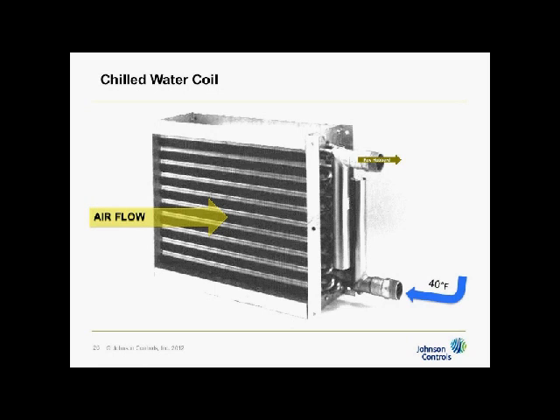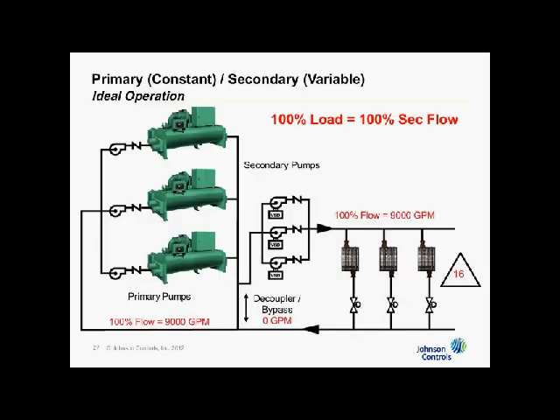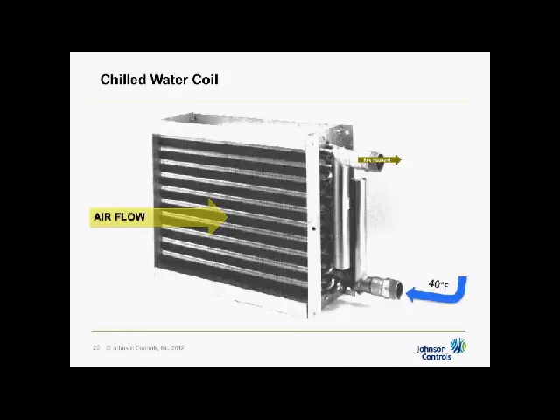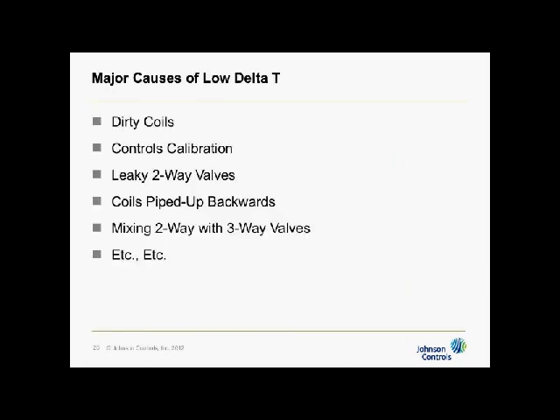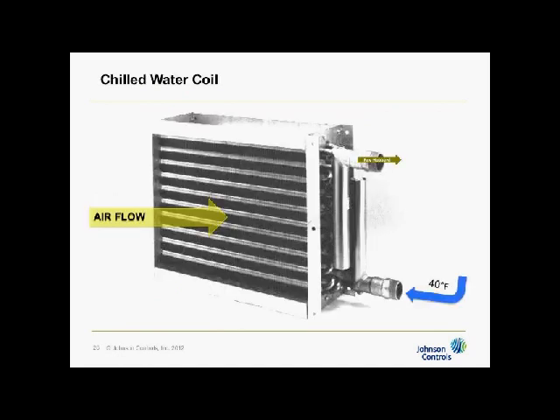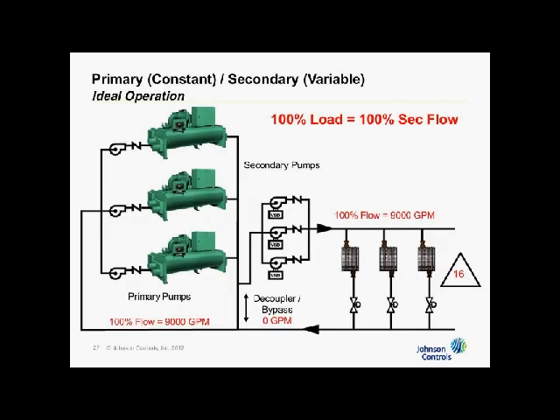So I can't pull out the delta T, the 16 degrees on this coil, and deliver 56 back to the system. It's going to deliver something less. And the same thing happens with all the other different things that were wrong with low delta T back here. All these things cause some sort of increased flow. So flow is out of proportion. You have more flow than a load needs. Okay? So now let's take a look at what that means.